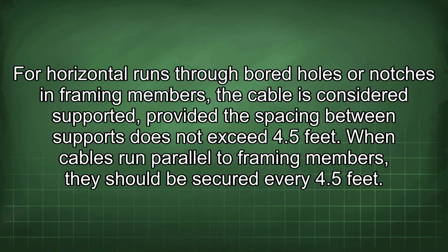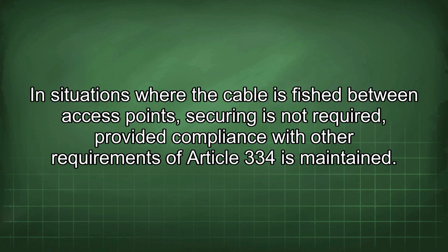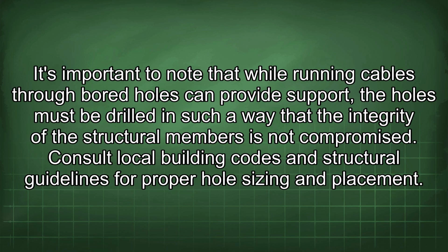For horizontal runs through bored holes or notches in framing members, the cable is considered supported, provided the spacing between supports does not exceed 4.5 feet. When cables run parallel to framing members, they should be secured every 4.5 feet. In situations where the cable is fished between access points, securing is not required, provided compliance with other requirements of Article 334 is maintained. It's important to note that while running cables through bored holes can provide support, the holes must be drilled in such a way that the integrity of the structural members is not compromised. Consult local building codes and structural guidelines for proper hole sizing and placement.